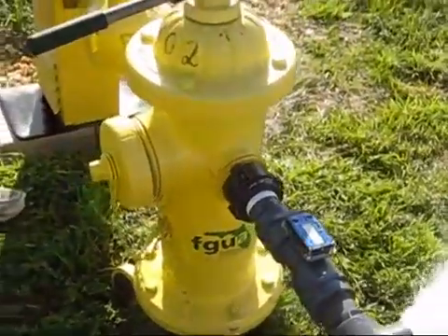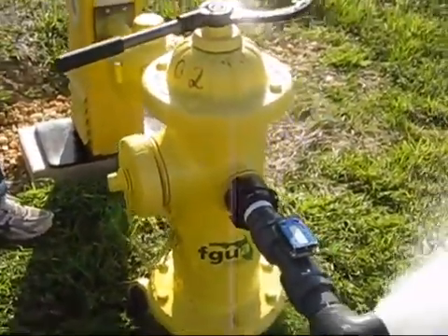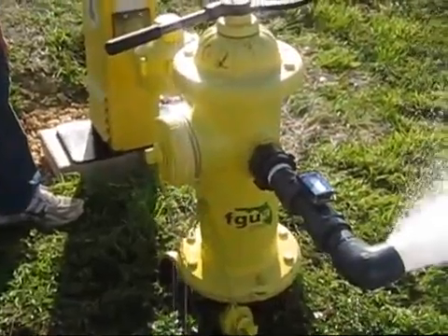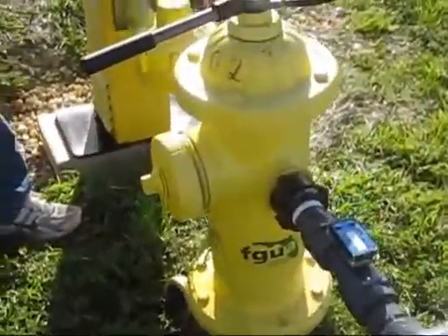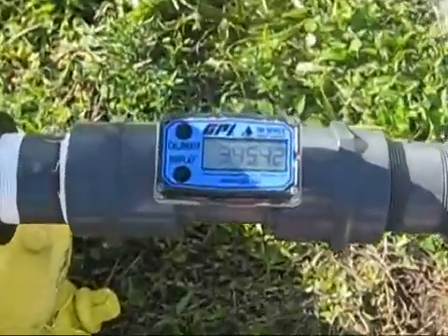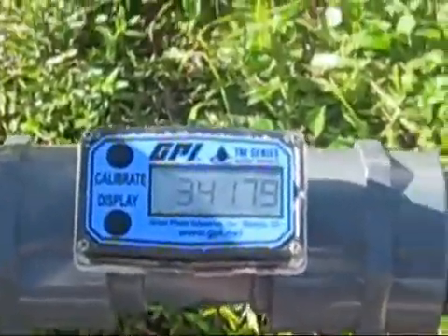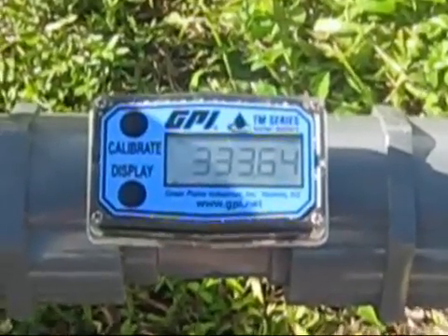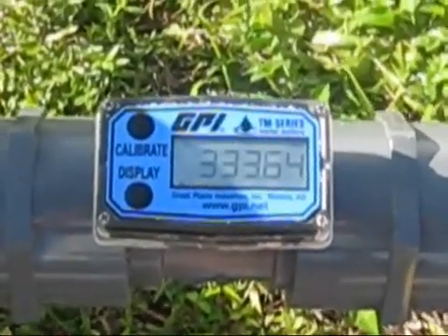Upon arrival, fire personnel should immediately shut down the HG6-equipped hydrant prior to attempting to attach any hoses to that hydrant. Once a hydrant is shut down, the hoses are attached, and the hydrant can be recharged for use. In the event a pre-scheduled flush program activates the HG6 attached to the hydrant being used to extinguish a fire, the flow rate from the remaining two connections will provide adequate fire flow volume.